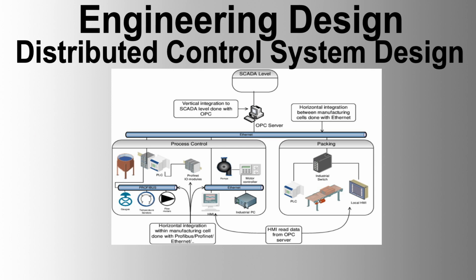11. I/O requirement. Analog inputs must process specified signals from independently powered or DCS-powered field devices, capable of processing signals from smart transmitters. Discrete inputs must be from volt-free contacts, loop-powered from the DCS, with contact bounce suppression. Analog outputs must generate 4 to 20 mA 24 volts DC outputs, handle smart devices with HART protocol, and be protected from short circuits. Discrete outputs must be loop-powered from the DCS, provided with fused disconnects, and interfaced through interposing relay panels for electrical drives and panels.